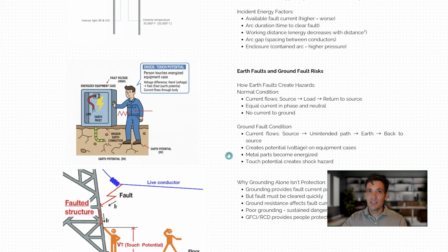and it's why you get a shock. So in normal conditions, the current flows from the source through the conductor to the load and back through the neutral or return path. In a ground fault condition, the current flows through an unintended path to earth, back to the source, or if there's no earth, you become that unintended path and you come up and you touch the piece of equipment. Now, touch potential refers to the potential the equipment frame could be at, assuming it's not earthed. If it is earthed, the resistance from the frame to the return path, so that earth bond might have some resistance in it, could have a touch potential.